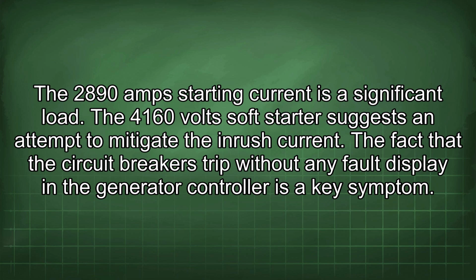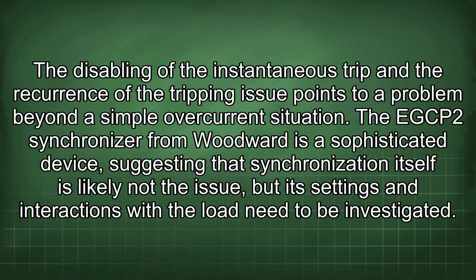The fact that the circuit breakers trip without any fault display in the generator controller is a key symptom. The disabling of the instantaneous trip and the recurrence of the tripping issue points to a problem beyond a simple overcurrent situation. The EGCP2 synchronizer from Woodward is a sophisticated device, suggesting that synchronization itself is likely not the issue, but its settings and interactions with the load need to be investigated.